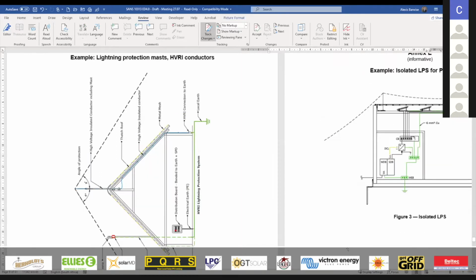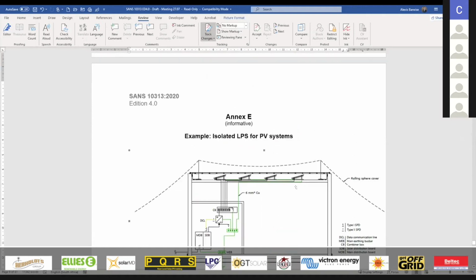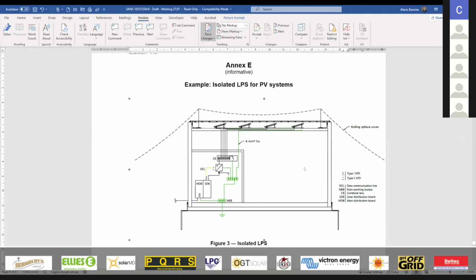So here you can see an example of an isolated lightning protection system for PV, and we've given quite a clear methodology to this. We isolate by the mast, we run the rolling sphere, making sure that we protect the entire solar system. Then we need only a 6 mil squared copper conductor, as we said earlier, because we're only dealing with induced surges.